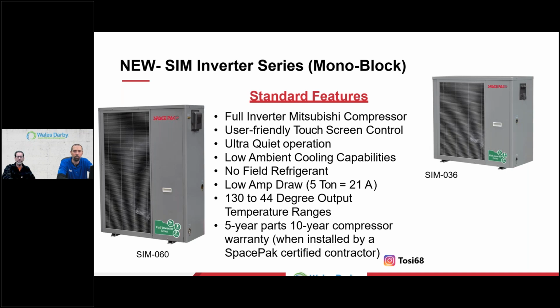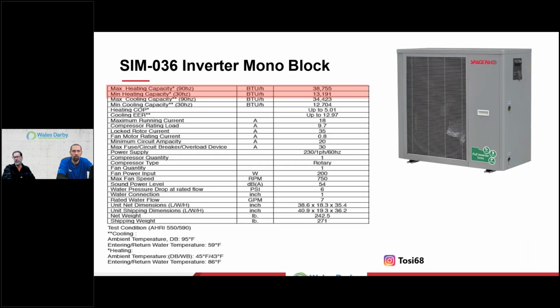So here's a little splash of what these things look like. It's an outdoor box with a coil, a couple of fans, and a compressor, with inverter technology using R410A at this point. They'll be changing to R32, as most manufacturers I'm aware of are doing. But yeah, 5 ton, 3 ton. We have some pretty big efficiencies here, showing you even some of the COPs, but be cautious. What was the COP achieved at during testing? It sometimes doesn't match reality.